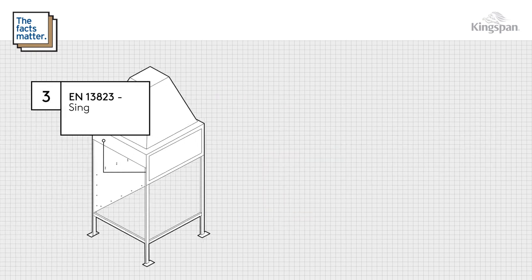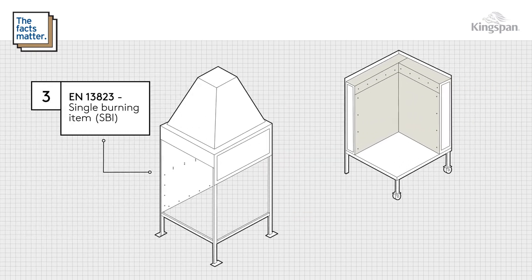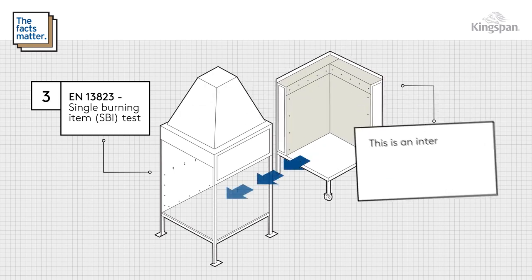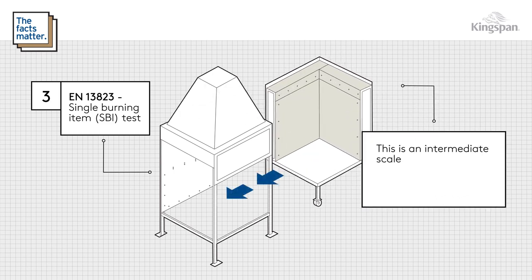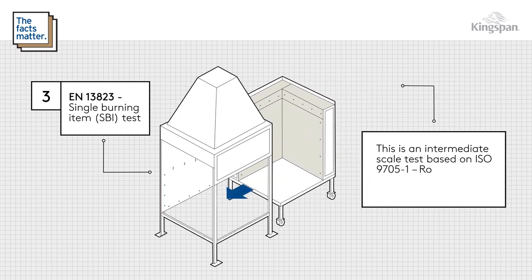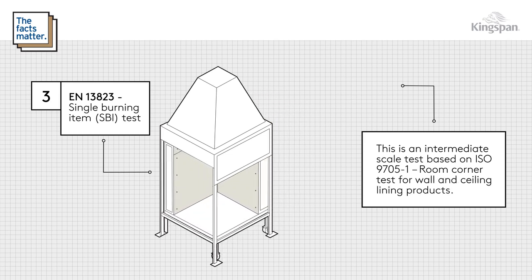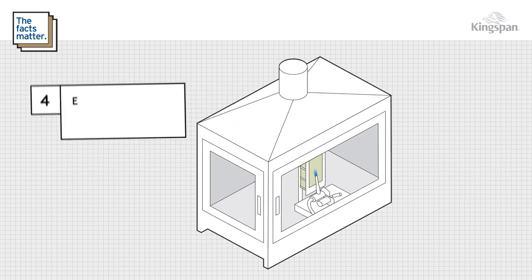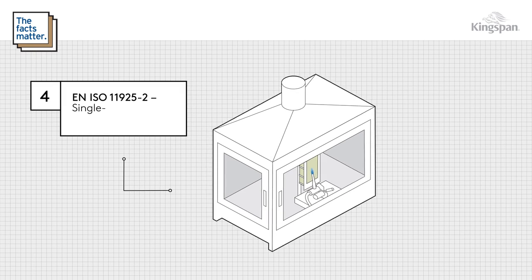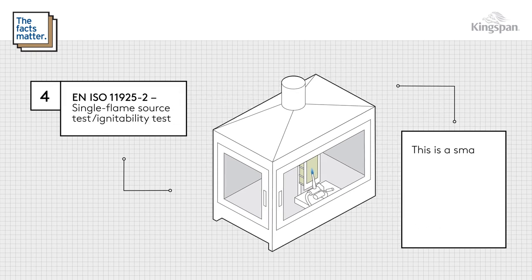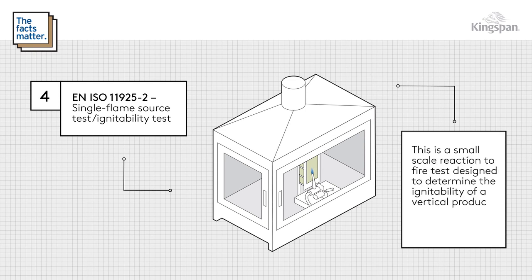EN 13823, the single burning item SBI test — an intermediate scale test based on ISO 9705 part 1, the room corner test for wall and ceiling lining products. EN ISO 11925 part 2, the single flame source test, ignitability test — a small scale reaction to fire test designed to determine the ignitability of a vertical product specimen when exposed to a small flame.